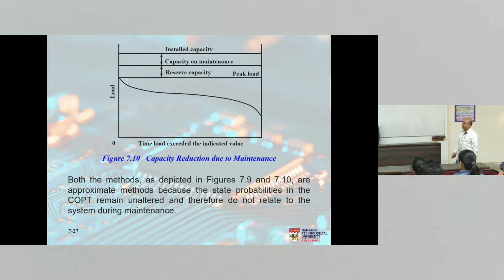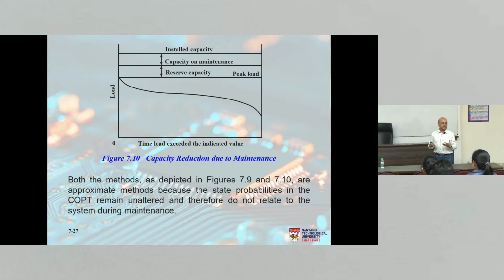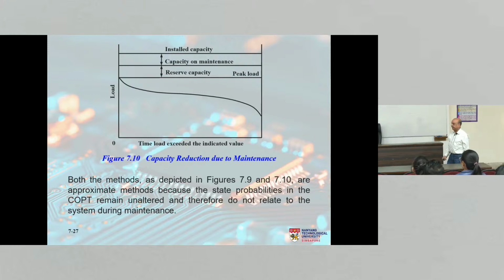That's one way. The other way is you have the installed capacity, and then you know the capacity on maintenance, so you reduce your total installed capacity to a new level. So your reserve in the system is much less now. So that's another way of treating this calculation using maintenance. There are various methods available in the literature, and the treatment of maintenance is not easy in terms of hand calculations. That's why I have not provided an example here, just the conceptual way of how you will introduce maintenance, okay?